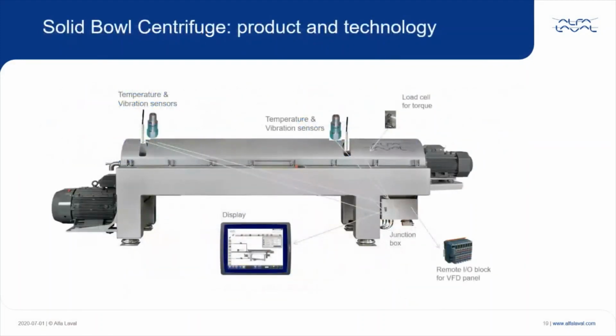The centrifuge is controlled using a state-of-the-art control system. As you can see on this slide, there are a number of different sensors, such as temperature sensor, vibration sensor. It has speed sensors and a load cell, and all this instrumentation is connected through a junction box to a PLC and VFD panel. It's also equipped with a large 15-inch touchscreen display, which is very user-friendly, and therefore the operators find it very easy to use. This automation helps in having good control of the equipment and making sure that the performance in terms of solids dewatering as well as the centrate clarity gets optimized on a continuous basis.